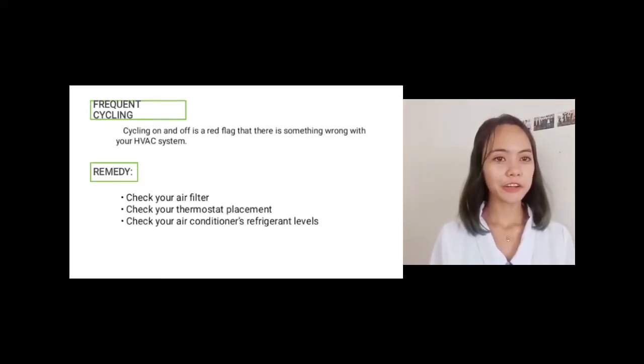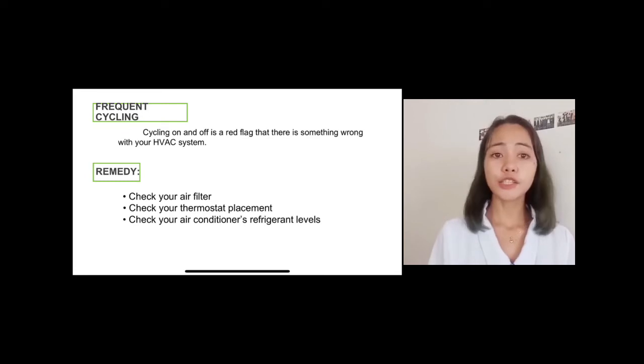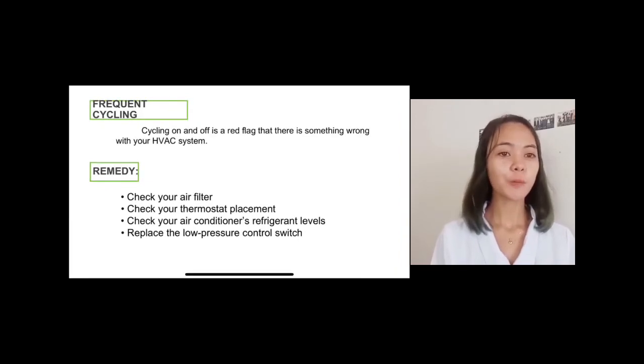Next, check your air conditioner's refrigerant levels. It's good to check the levels so you can track down any leaks within the air conditioning system. Then, replace the low pressure control switch. If you are still dealing with short cycling issues, replacing the component is an option. And lastly, check the compressor.